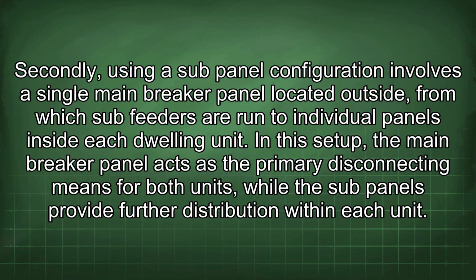Secondly, using a sub-panel configuration involves a single main breaker panel located outside, from which sub-feeders are run to individual panels inside each dwelling unit. In this setup, the main breaker panel acts as the primary disconnecting means for both units, while the sub-panels provide further distribution within each unit.